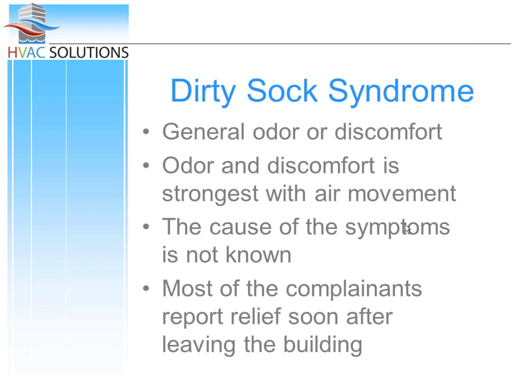One other problem that we run into is dirty sock syndrome. Now, this is where you walk into a building or maybe a home and it smells like a locker room. Doesn't smell fresh, that's for sure. So there's a smell, there's an odor going on. What I can tell you is that 9 out of 10 times they're going to come to you and say, hey, I've got mold somewhere. I don't know where it's at, but I can smell it. And what I can tell you is that 9 out of 10 times it's not mold.